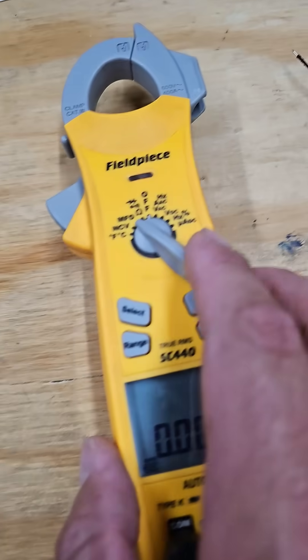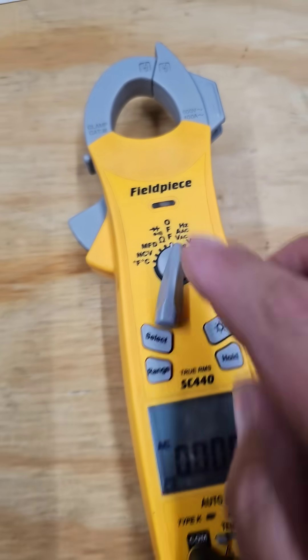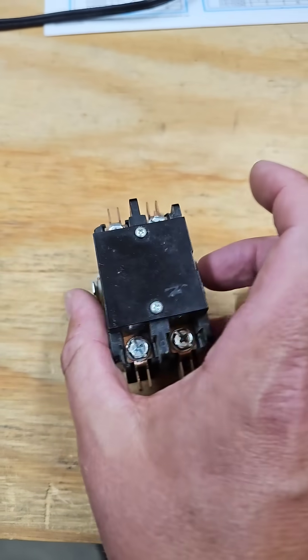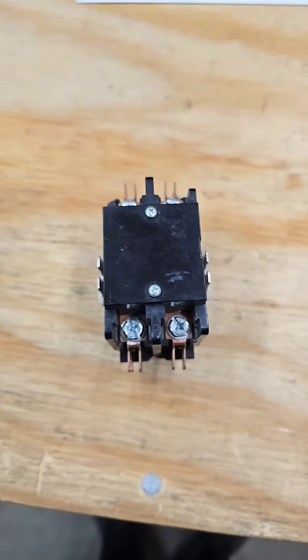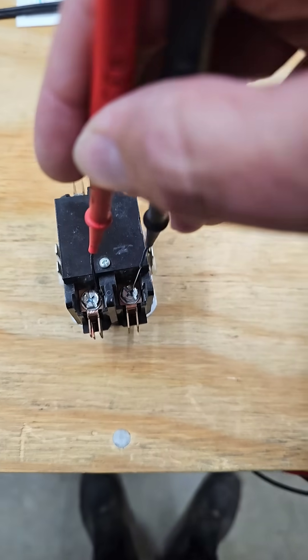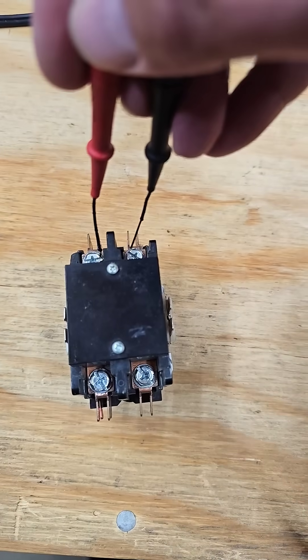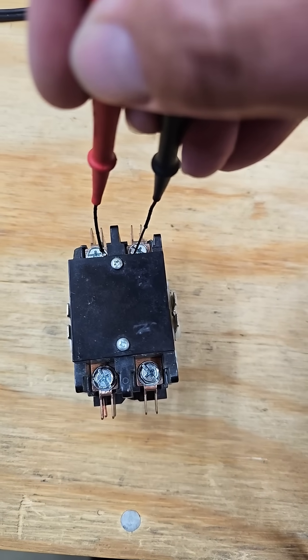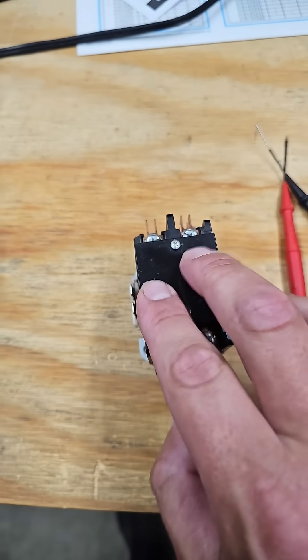To test a contactor during a call for cooling, you'll check volts AC at the coil. The coil should read 24 volts. When you have power to the coil, you should have line voltage in and line voltage out. If you check your line and it's 240 volts, and then you don't have 240 coming out, your contactor could be bad.